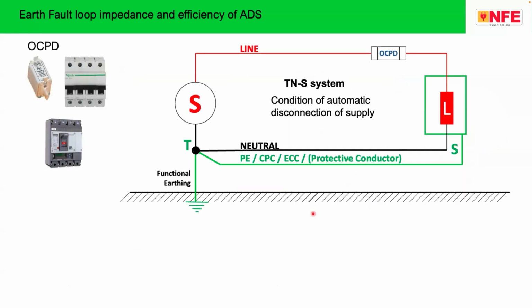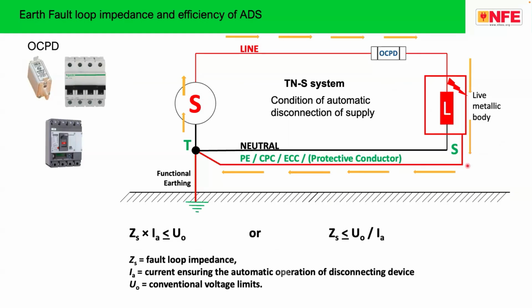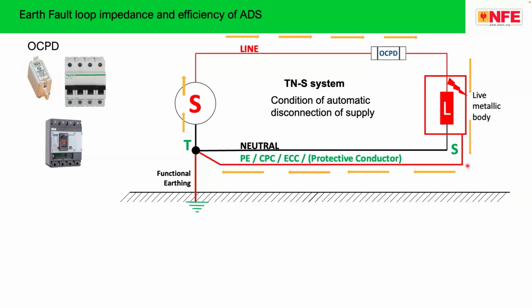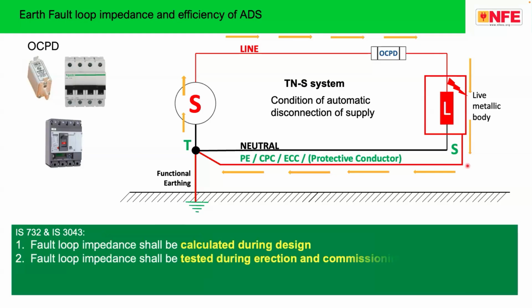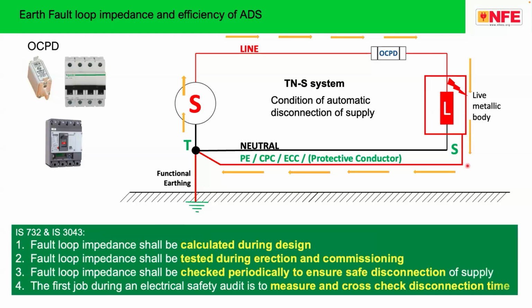Again, very well explained in the standard. You are supposed to make a TNS system. Means, as you can see in the single line diagram, there is a source, there is a line, the neutral returns back. The body of the equipment is connected back to the neutral of the transformer through a metallic conductor. This is called a TNS system. Whenever there is a fault in your equipment, the fault goes through this closed loop. Now the impedance of the loop comes into the picture, and this is called fault loop impedance.